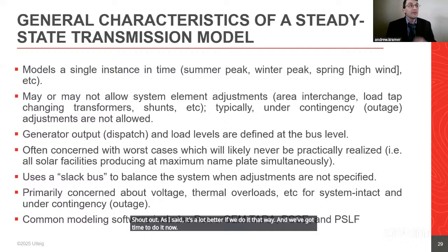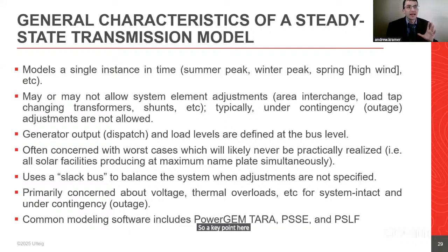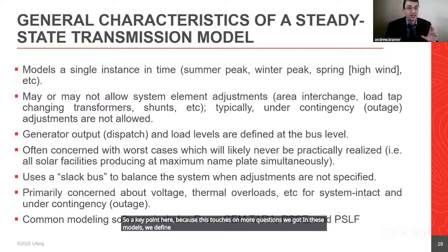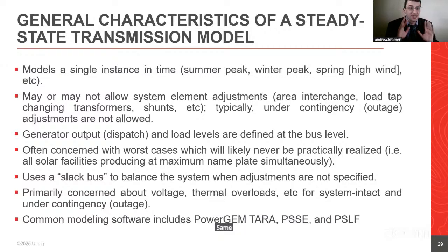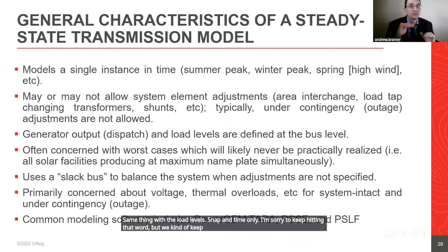A key point here, since this touches on more questions we got: in these models we define the generator output, also called dispatch. You tell the generators what to do. There are no economic decisions being made here. Same thing with the load levels. It's a snapshot in time only. It does not adjust and move the generators up and down, you have to tell the model how to do it.